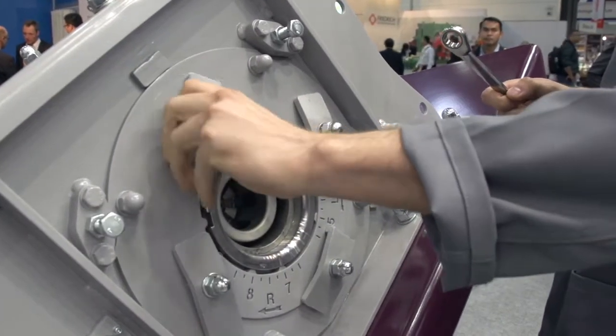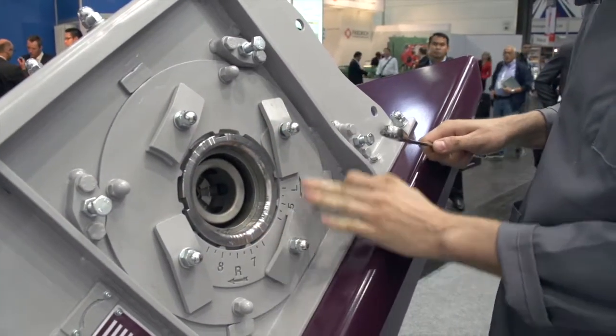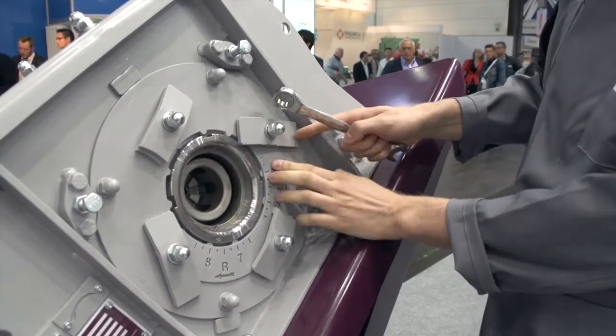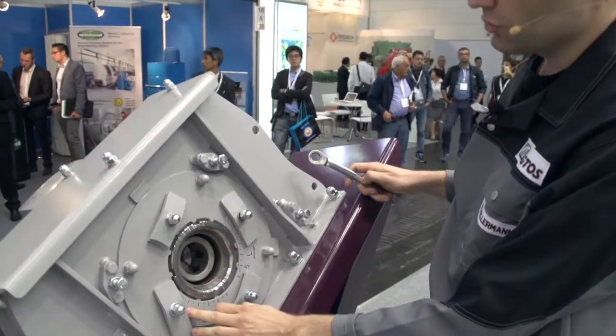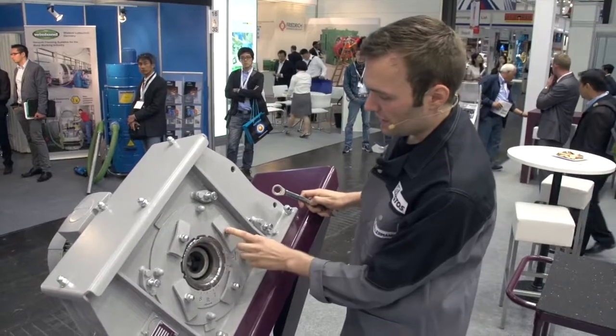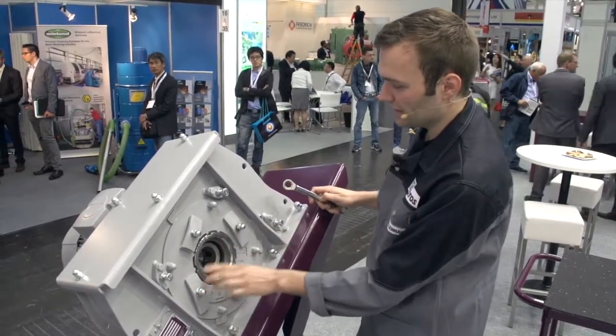Prior to removing the guiding sleeve, note down the setting. There is a mark on the turbine housing. It indicates the settings from 3 to 9. In our example, the guiding sleeve is set to 7. The notch on the edge of the guiding sleeve should be aligned with the specified mark on the turbine housing.